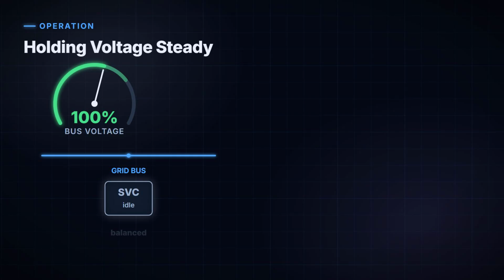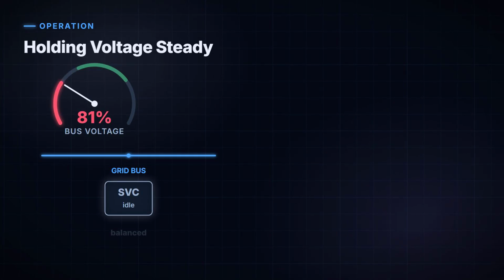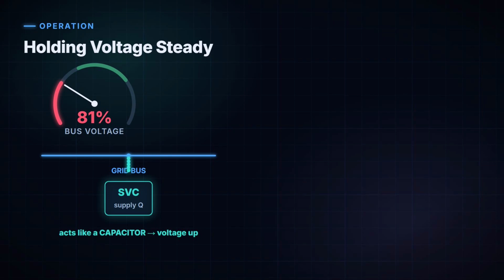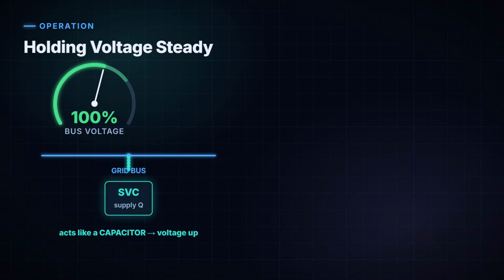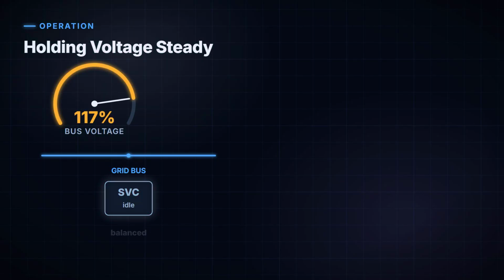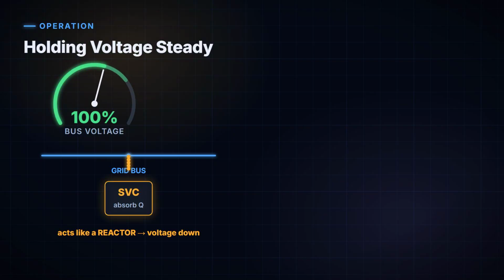Let's see them work together to actually hold the voltage steady. Picture the grid voltage starting to fall, maybe a big load just switched on. The control system reacts. It switches in capacitor banks and backs off the reactor. So the SVC pushes reactive power into the grid, like a capacitor, and the voltage comes back up. Now picture the opposite. It's late at night, the load is light, and the voltage starts creeping too high. The SVC fires the reactor harder, absorbing reactive power like an inductor, and pulls the voltage back down.